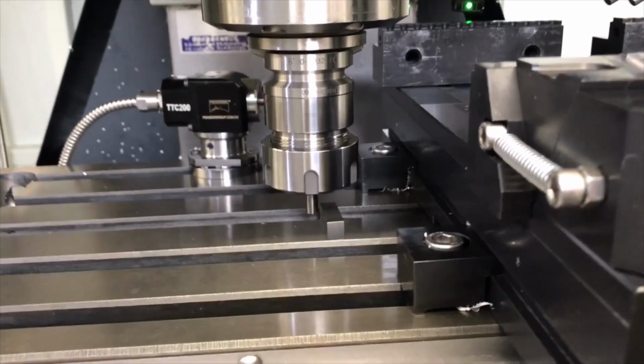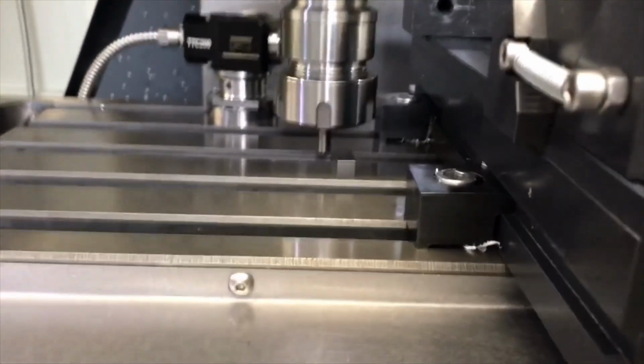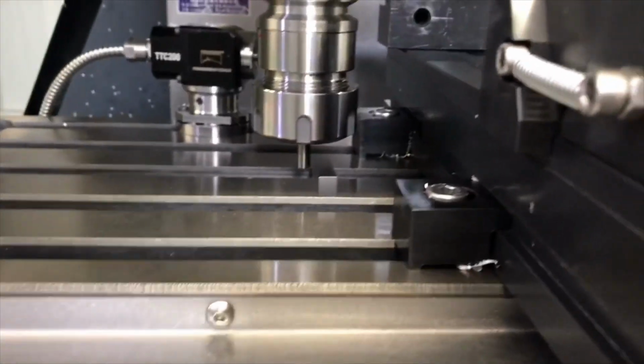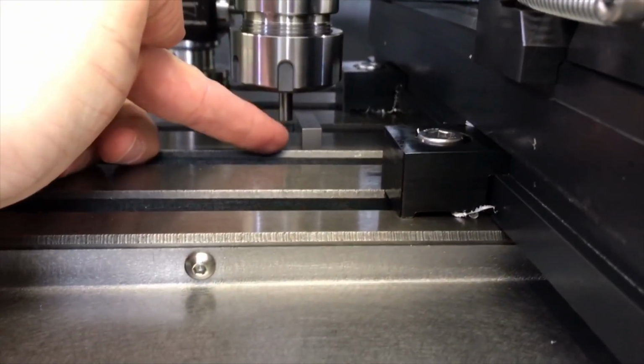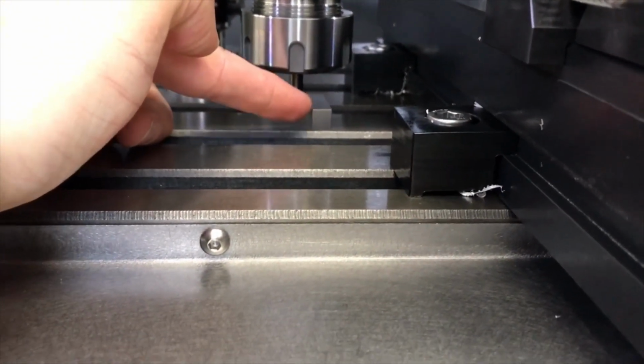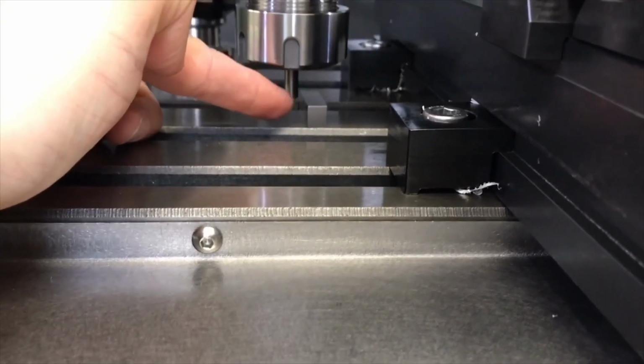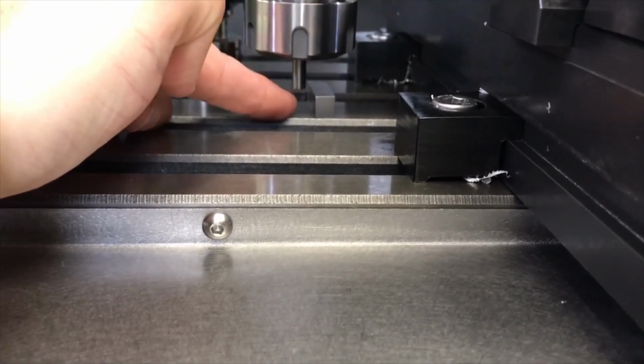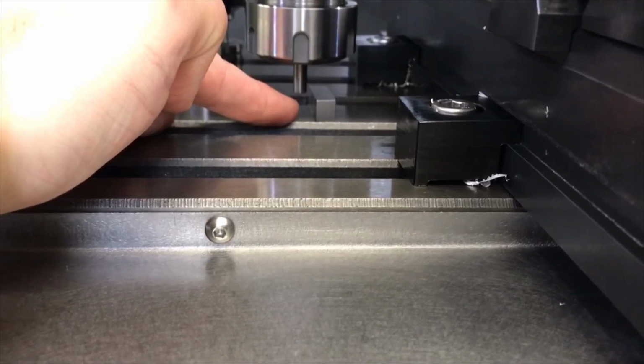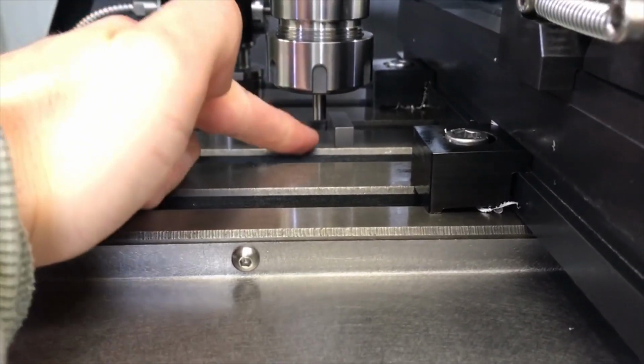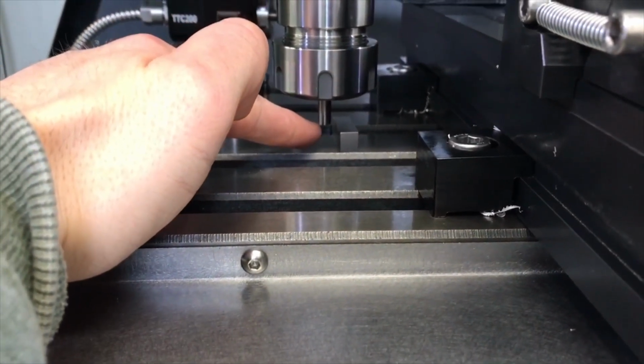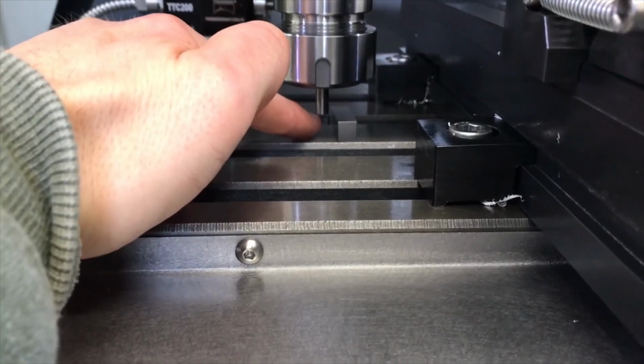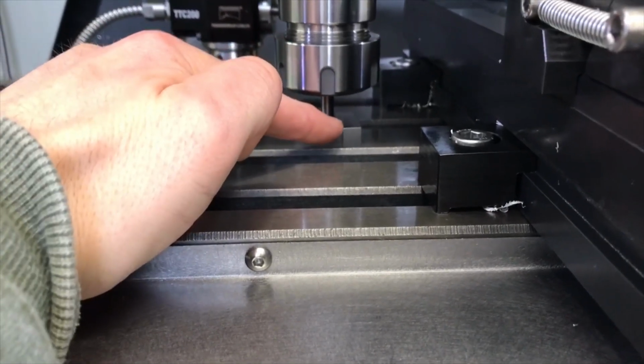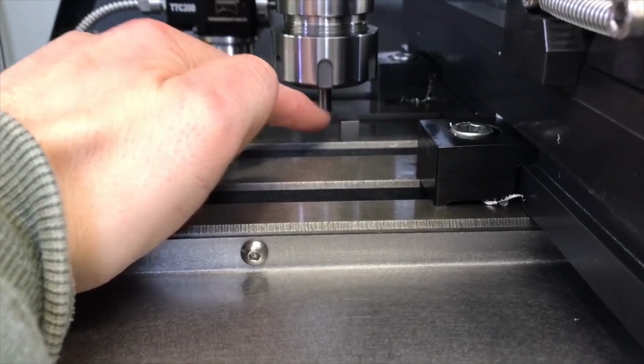Okay, so now I've jogged the machine down and I've set the height of the master tool so that the block can slide under it. If I jogged 1 micron down right now, the block would not fully slide through. So I am happy, to within 1 micron, that the current location of the tip of this tool is at the top of this gauge block.